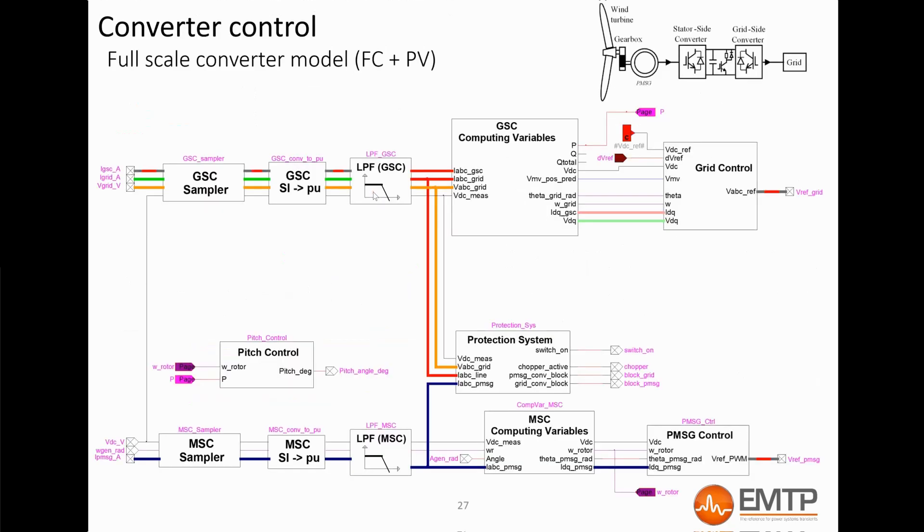Here is the control and protection diagram of the FC wind turbine in EMTP. The sampled signals, which are the voltage and current on each side of the converter, are put in per unit and filtered. The input measuring filters are low-pass type. The compute variables block computes the variables used by the FC control and protection system. In these blocks, you will find PLLs, which are algorithms which determine the voltage angle and frequency and help to achieve the transformation from the ABC domain to the DQ0 domain, which is used for control purposes.